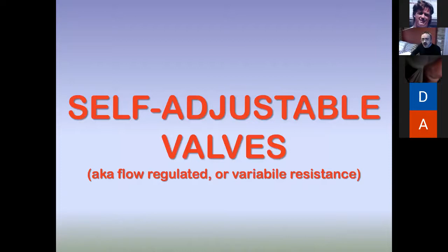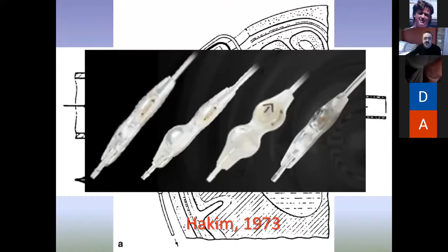Other attempts were made to create a self-adjustable valve, and this is the first one, created in 1973. You can see in the picture a sensor connected to the valve, and this sensor in the subarachnoid space can check the pressure there, and by a system with the ball cone, reduce or increase the resistance. Also created by Hakim in 1973, this is the commercially available self-adjustable valve, also known as Orbis-Sigma valve.